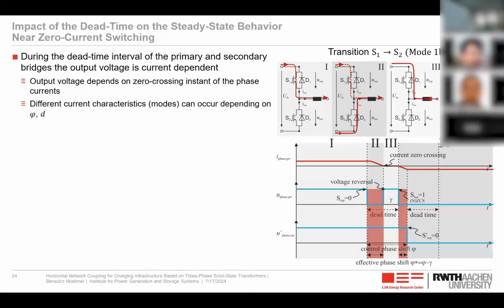And this voltage reversal here with the time interval gamma causes then a reduction of the phase shift. So the effective phase shift that we apply is reduced. And in this case, we are not realizing 0 voltage switching, but somehow near 0 current switching, because this current can be around 0. However, the secondary side is still soft switched under this condition.